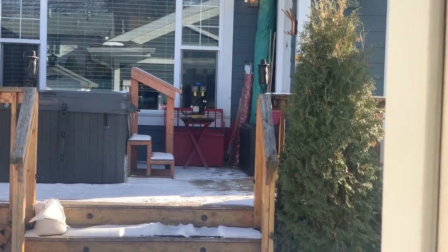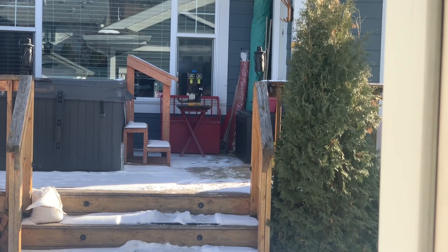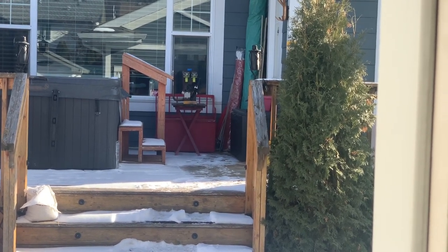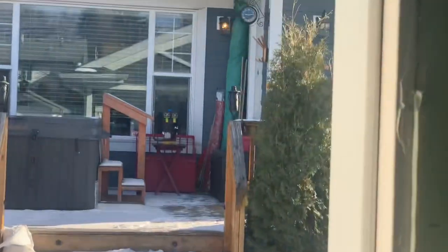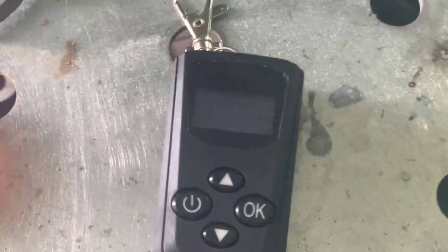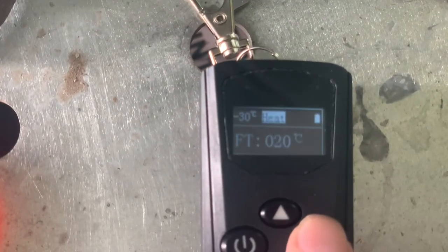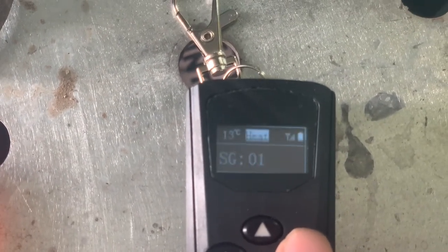Steam just stopped, so that should mean it's lit. I can't even really hear it from here, and here's the distance I am. Garage 2, there is probably about 30 feet. Well, I think I can hear it now. Let's see if the temperature starts to climb on the old meter here. Remote. 16, 18, yep, she's lit and burning. 20, and I've got it set for 1.